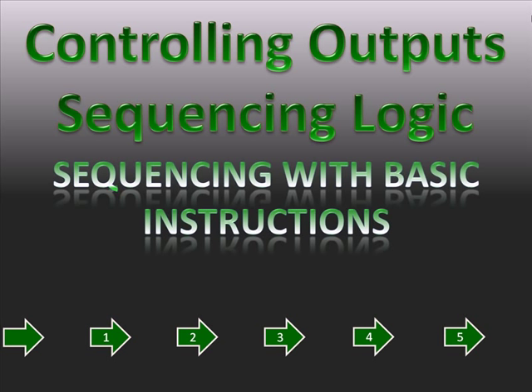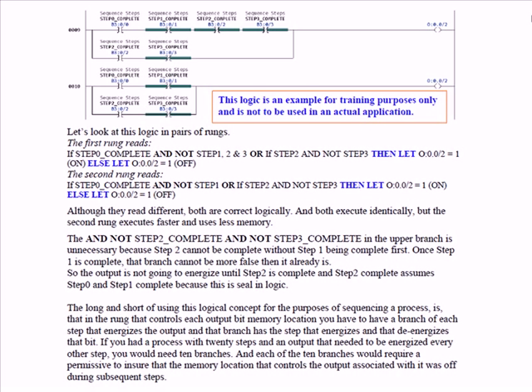In your lab we had you put in these two rungs, rung 9 and rung 10. Notice that both rungs had the same memory location addressed by the OTE instruction, so either rung turns on what we'll call output 2. Both of these rungs behave identically. I just wanted to illustrate that sometimes we have more instructions in the rungs than we actually need. In rung 9, if step 0 is complete but not step 1, not step 2, and not step 3, then turn on output 2.